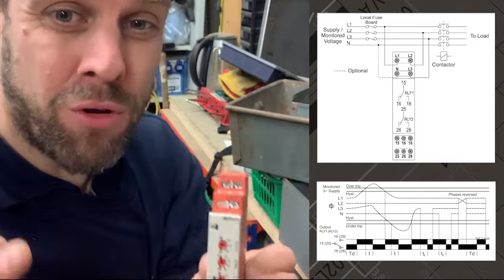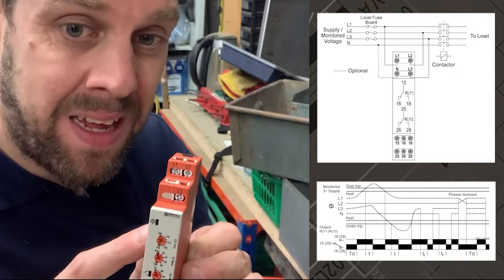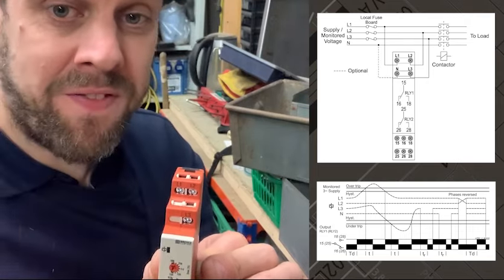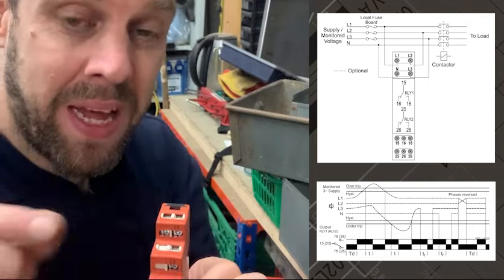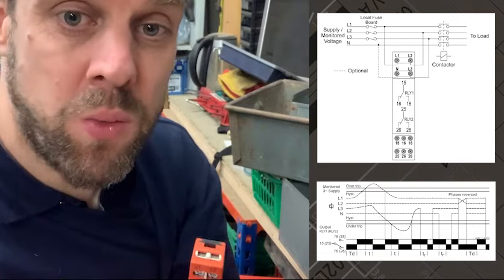Other ones will monitor single phase and neutral and that kind of thing, because if you've got a pump that must run but could be damaged if it runs on two phases, you can have one of these sat there when the pump's not running monitoring the phases. Then if for any reason the phases disappear you can sound an alarm and you find that out in advance, not when you want the pump to start.